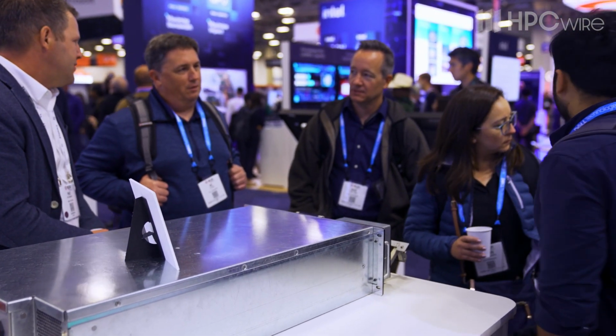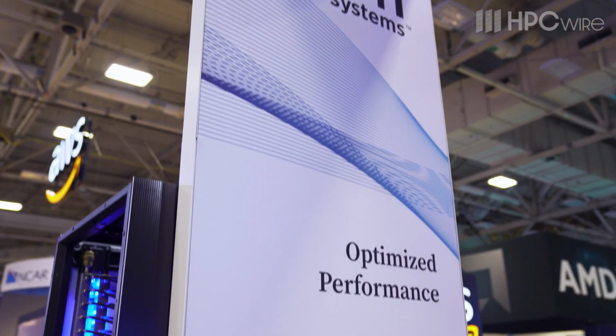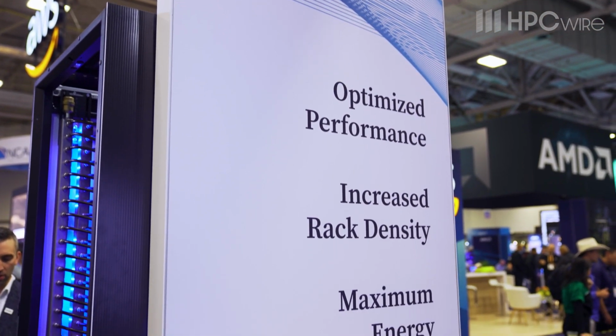CoolIT Systems is the leading designer of direct liquid cooling for data center applications. We do everything from the liquid cooling inside the servers, which we call the passive cold plate loops, all the way out to the data center infrastructure side, so the manifolds, cooling distribution units, and all the services associated with delivering direct liquid cooling into data centers.